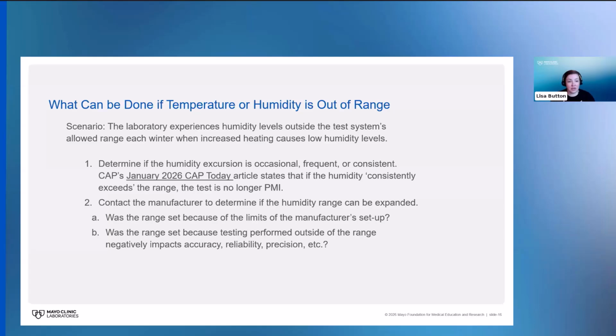So the first thing that you would want to do if you were the quality or technical specialist, maybe the supervisor of the lab that is experiencing this, is that you would want to determine if the humidity excursion is occasional, frequent, or consistent.